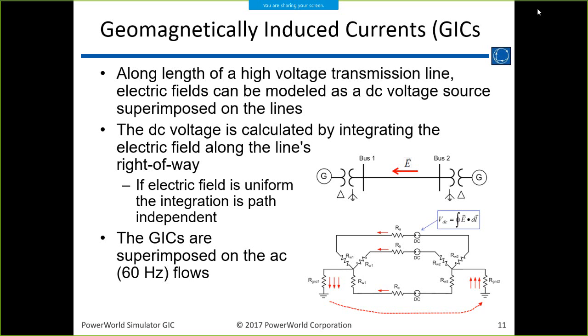Now, sometimes people will raise the question, what resistance are you using there, the 60 hertz resistance or the DC resistance? The values are different because the skin effect at 60 hertz makes the resistance appear a little bit higher. But with all the other uncertainties in here, you usually just use the AC resistance and you're okay. Another quirk is that the resistance of a wire, be it aluminum or copper, changes at 0.4% per degree C.